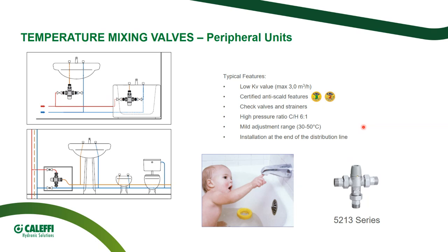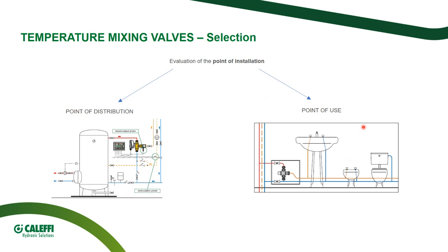The adjustment range is lower than before. We are speaking from 30 to 50 Celsius degrees, and they are installed at the end of the distribution line just before the final users. So when designing a project, we decide to input in the system a temperature regulating valve. First of all, we have to ask ourselves, where do we have to install it? At the point of distribution or at the point of use? So this already allows us to identify a certain product range different from the others.